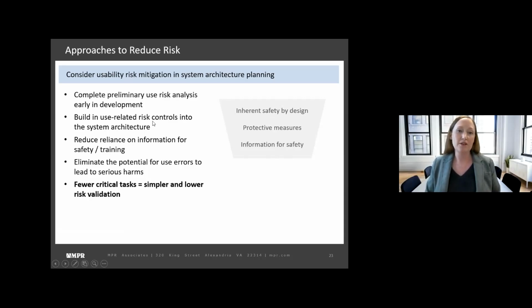So by thinking about use-related risk controls and how we can integrate them into hardware or the system design early on to really eliminate potential use errors, we can reduce the reliance on information for safety or training that might need to be validated at the end of development, and ideally eliminate any potential for use errors to lead to serious harms. Thinking about this early and really building the usability risk mitigations into the system can help us have fewer of those critical tasks that we need to evaluate in validation, which means a simpler and lower risk validation at the end of development.